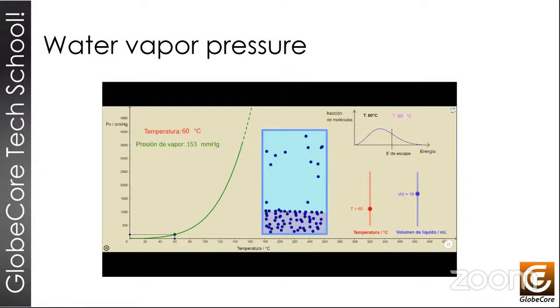But the moment we remove the particles from the gas, there is no more downward pressure exerted on the surface. And so any impact or motion of molecules will cause them to separate from the liquid into the gas phase. And that allows water that's on the surface to be easily detached and absorbed by our vacuum equipment. And that's how we do dehydration and even degassing of oil, because it also works for gas. It's very important to ensure that the higher the vacuum we reach, the more water we can extract at lower temperature. And this process is much more efficient on the surface. So we need to maximize the surface area, the contact area between the oil and the gas phase. And there are two ways to do it. We can do it laminar, or we can spray the oil. Next slide, please.